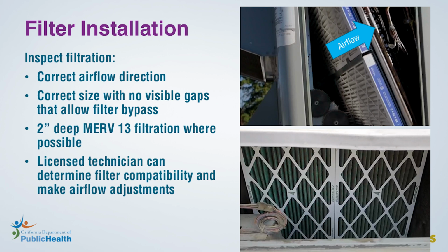As discussed in Module 7 of the series, you'll want to use 2-inch deep filters with MERV 13 filtration wherever possible and change them every 3 to 6 months. If you are unsure if your system is compatible with MERV 13 filtration, a licensed technician can measure the total airflow through the system and the pressure difference across the system fan to determine filter compatibility.